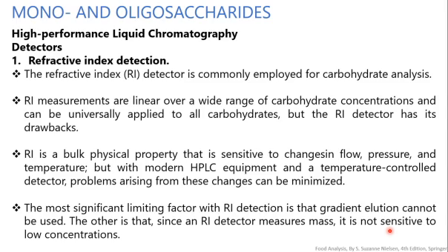Generally, refractive index is associated with some kind of physical property, from which we can get an idea about the density. So as there is a change in pressure, flow, and temperature, the particular density, or we can say the refractive index, will be different for different kinds of solutions. If you change the concentration of the solution, that RI becomes different. So it will affect the analysis.